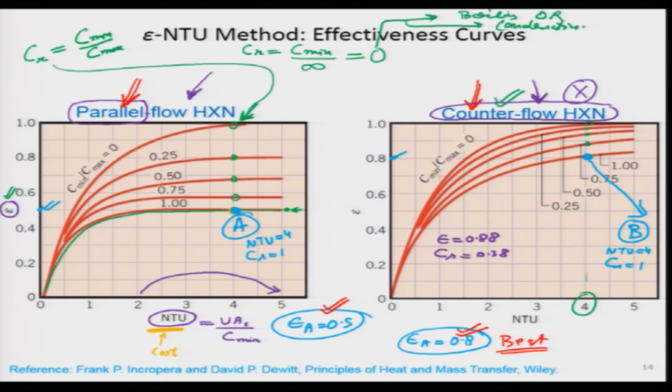Now, I will continue with the purple color over here, epsilon 88%. I am going to assume it is very close to 90, so this is the line I am on. This is my x axis, and I have to figure out the C_R value from here. 38% is somewhere between 25 and 50%, so somewhere in the middle I am over here. If I choose this particular point, it is not bad actually.